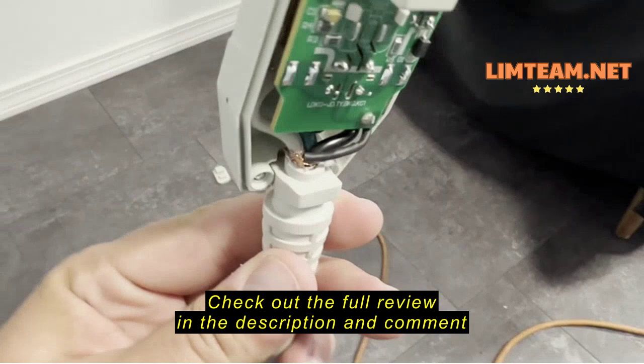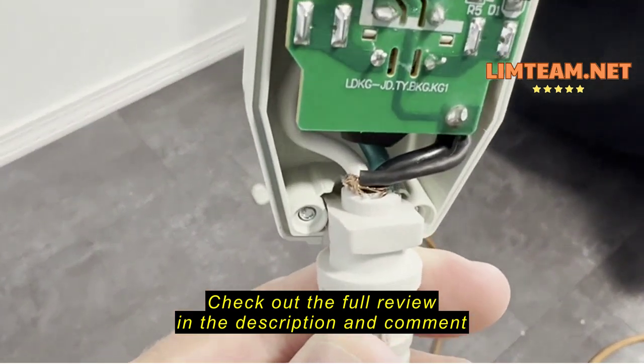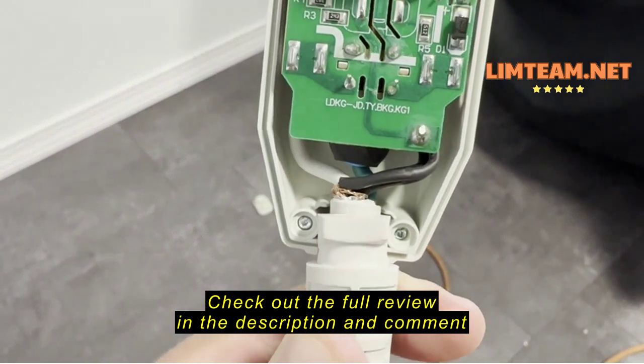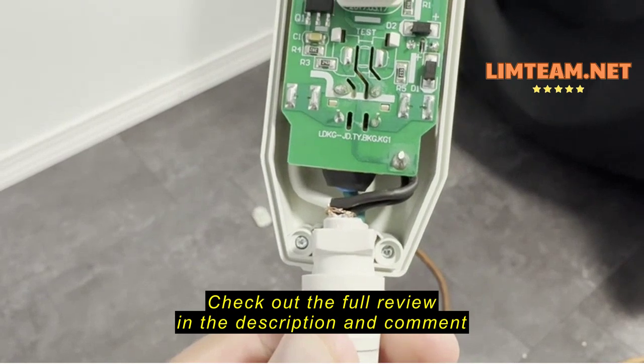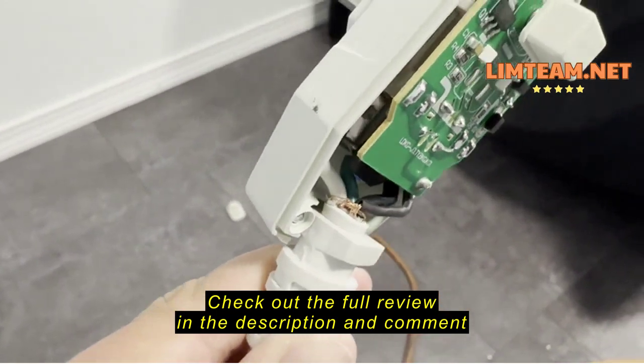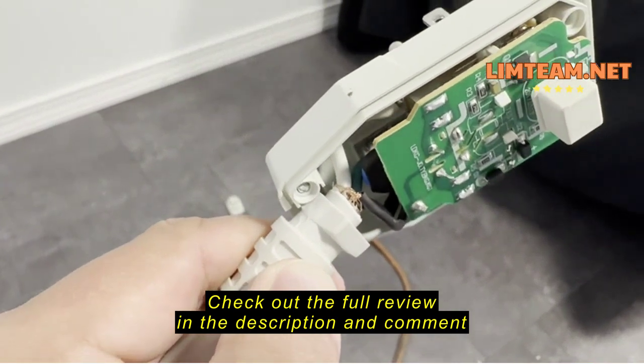Anyway, all right. Took a GFI apart, and you've got exposed wires, which are heating up. Power wires, and they're touching the shielding of the cord. And there's not enough current carrying capacity because so many strands are broken.